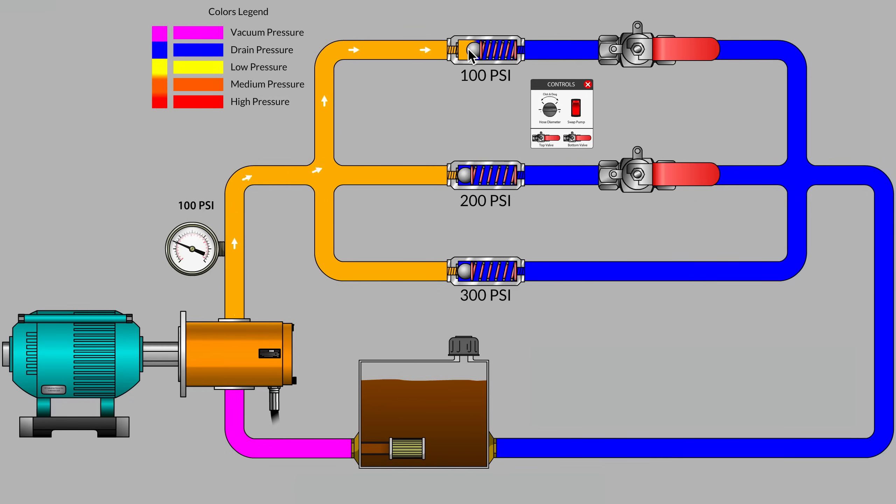So that's a bit of an introduction to what happens when you have more than one parallel flow path in a hydraulic circuit and you're expecting flows to occur on more than one branch. Typically, the path of least resistance will come into effect whenever oil can find the easiest path back to tank. It will take that route and that will be reflected as the system pressure on our main system pressure gauge.